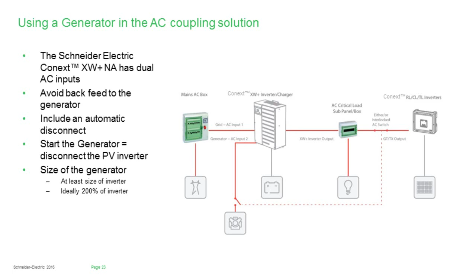Again, that sizing for the generator, and the thing we want to note is that it should be at least the size of the inverter. We size the inverter for the loads. We should size the generator at least for that. But we want to make sure that if the batteries get low, that the generator just doesn't simply take over the amount of power that's being consumed, which means that we'll never actually get any charging done and get that system turned off. So ideally, if we can double the size of the generator, then the generator is going to be able to provide not only for the loads, but also be able to provide for charging for that system.